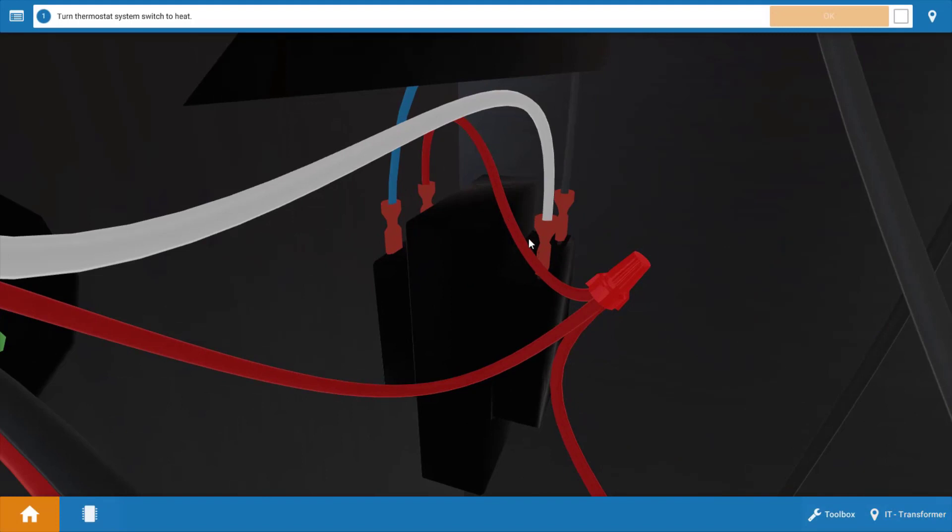Now the transformer provides 24 volts for the gas valve and the control circuit of the boiler. You have 120 volts on the primary side here and it induces the 24 volts on the secondary side.